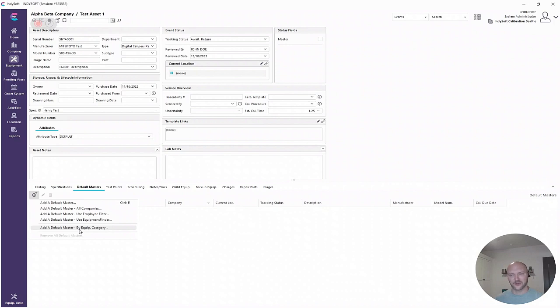And when we pop open a calibration event, we basically would show you a filter. So this use case that I'm going to go after really is, I have a workstation and I always use these X amount of calibration standards because I'm doing the same thing all day. So maybe pipettes, right? Really good use case there. Could be a number of other places. Could be used in various torque applications as well. But anywhere where you're going to be using the same things over and over again.